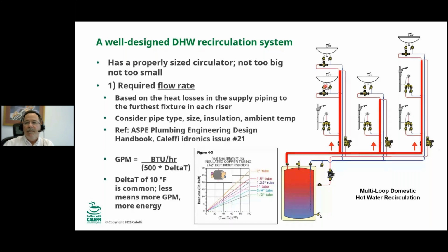So what you do is you start at the heat source. If you can see my pointer here, for this first riser, we're going to start right here and go up, across, and up to the end of this. We're going to use that section of piping to calculate a GPM based on the delta T and then the BTU per hour per foot of heat loss in that one run of the piping system. So you will come up with a GPM for this piece here. The second piece is right from here, at the bottom of that first riser, over and up. The second piece is this section of piping.